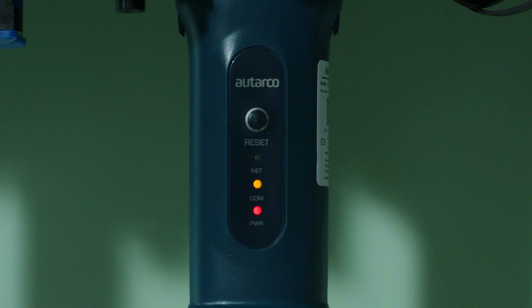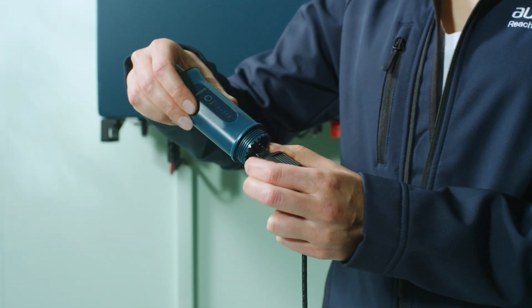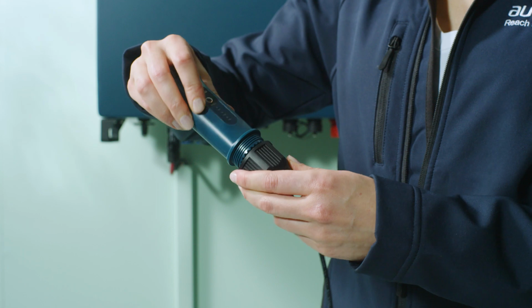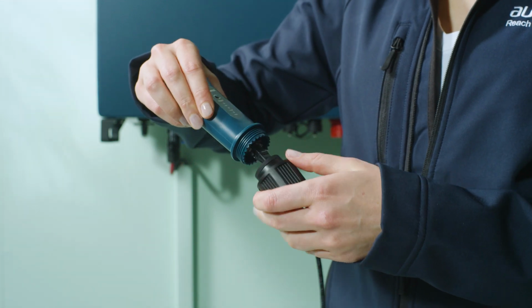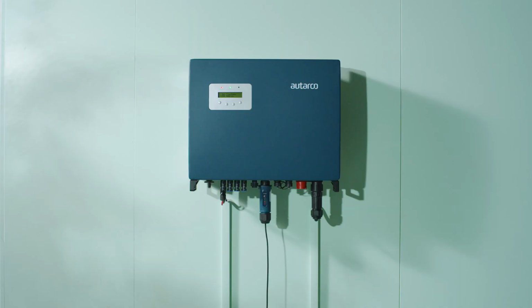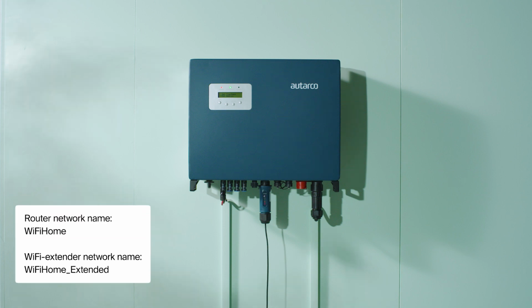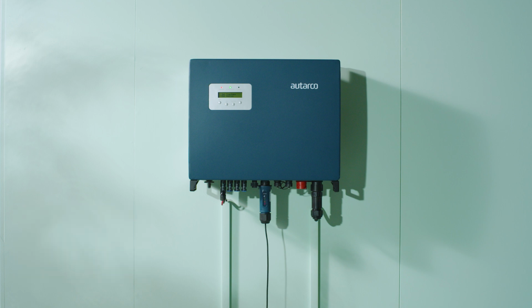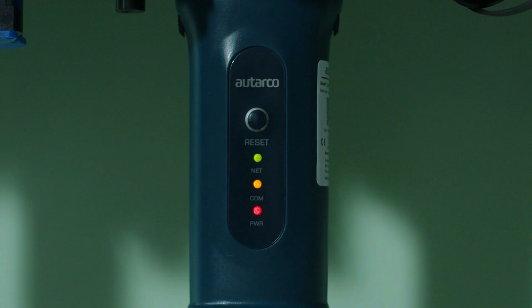If that's not an option, install one or more Wi-Fi extenders between the local router and the inverter, or use a wired network connection. Ensure a Wi-Fi extender's network name differs from the router's network name. This can be any name, for example by adding the text extended to the original network name. Doing so ensures that the LAN stick connects to the extender and not directly to the router when choosing a network from your network list.